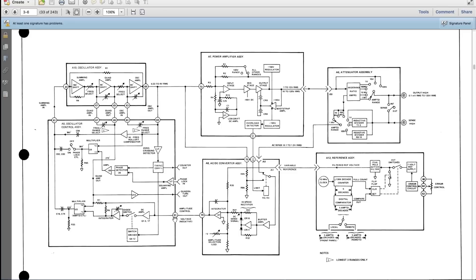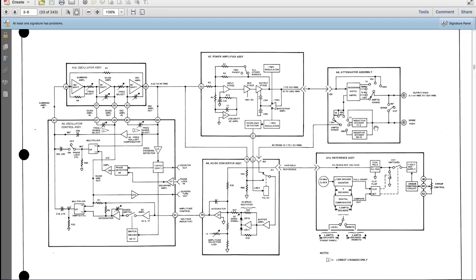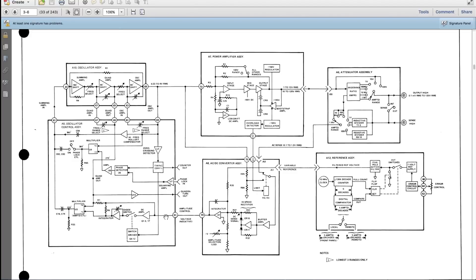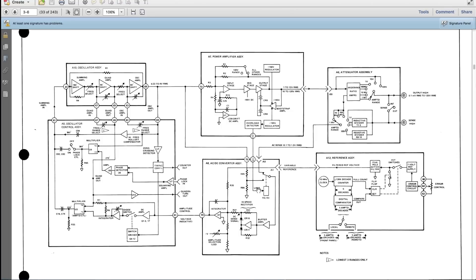This may or may not be working correctly, but is that because there's no amplifier control from here? Now I've actually measured this test point here at connection 51, pin 51 on the card, and that is reading zero volts. And it's supposed to be between minus 15 volts and zero volts. So zero volts to me says it's fully out of one range. And that's without the amplifier installed, because that's blown. So everything's blown. Reference assembly is fixed. I've already repaired this and I'm 99% sure this card is good now.